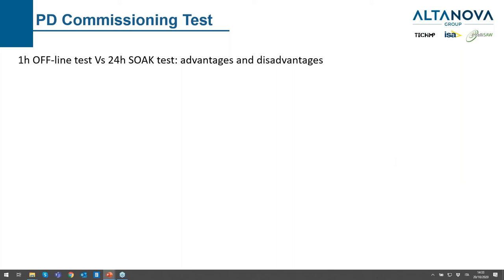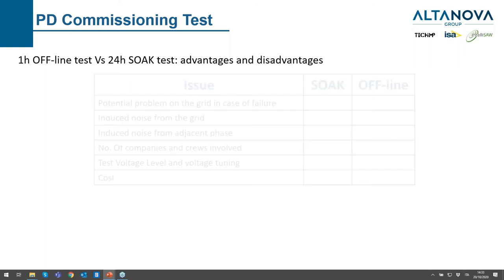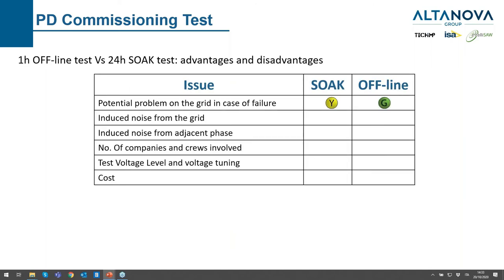Comparing the offline test at different voltages — above rated voltage for one hour — versus the 24-hour soak test: there is a potential problem on the grid in case of failure with the soak test. In the offline test, the cable is connected to a resonant testing system (RTS), so we are not connected to the grid and not affecting anything on the grid side. From the PD point of view, in the soak test there can be noise induced by the grid, whereas in the offline test we don't have that problem, mostly because we operate outside of 50 Hz or 60 Hz using the resonance frequency — so PD phenomena are referred to the resonance frequency, not 50 or 60 Hz.